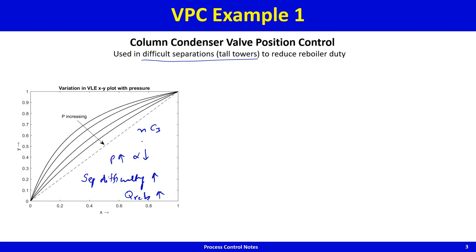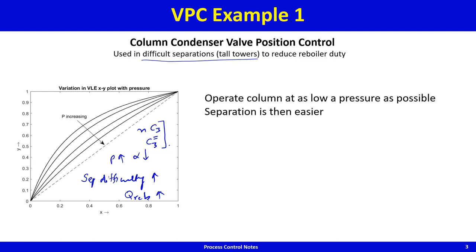A common example is the C3 splitter that separates propane and propylene — a low relative volatility separation requiring perhaps 200 trays. In these tall towers it is beneficial to run at as low a pressure as possible, because the lower the pressure, the greater the relative volatility, the easier the separation, and the lower the reboiler or refrigeration duty.